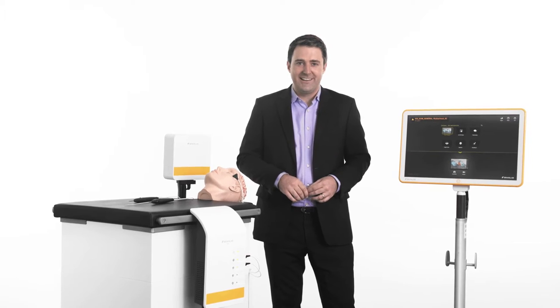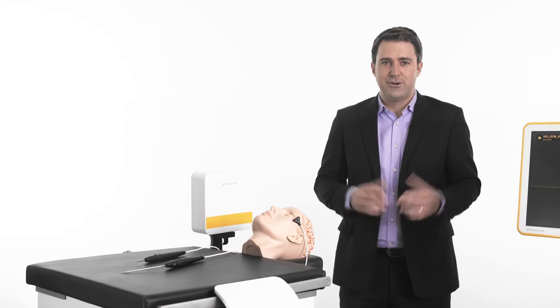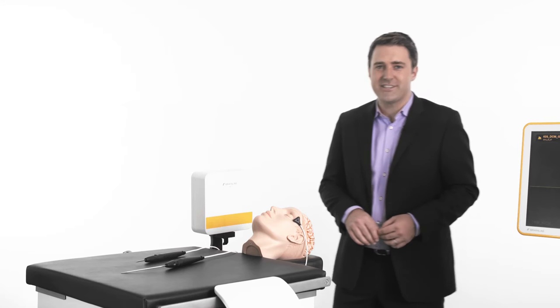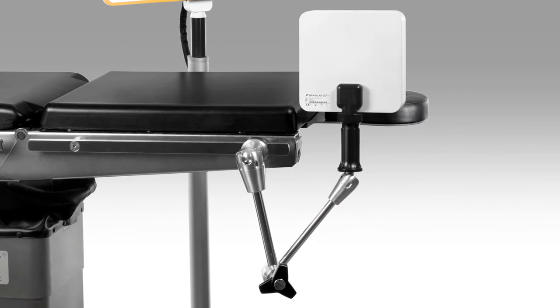This is KICK EM Cranial, electromagnetic surgical navigation for straightforward pinless procedures. To address various positioning needs, the tracking unit generates a large electromagnetic field of around 50 cm in all three dimensions. Its articulated arm allows for optimal placement of the tracking unit near the patient's head.